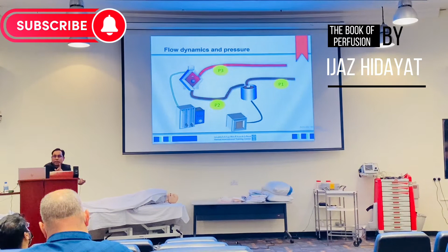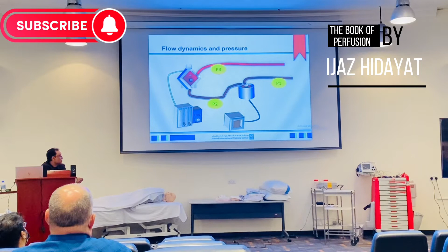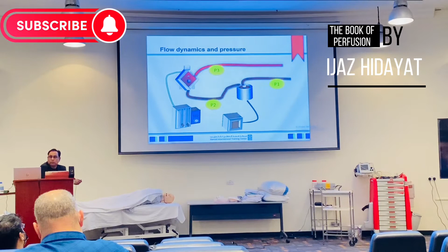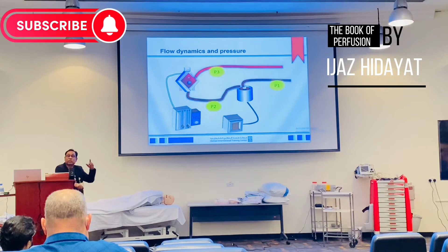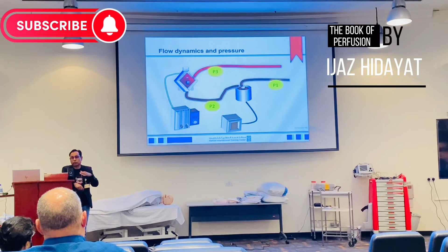Number two is your P2 pressure. P2 pressure is your pre-membrane pressure, and pre-membrane pressure is higher than your post-membrane pressure. Anyone answer why? Yes, there will be the pressure. So this is the reason the P2 and P3 difference is your TMP pressure, which you will get after a resistance here. So if you are, for example, at 150 pressure, with the resistance your pressure will be something like 150 and 130. So 20 will be the delta P, the transmembrane pressure, and transmembrane pressure is the pressure that will guide you whether your membrane is failing or it is okay. So ideally your TMP pressure should not be double your baseline. It should not exceed more than 50 millimeters of mercury.